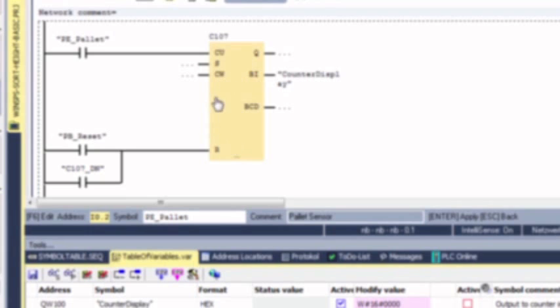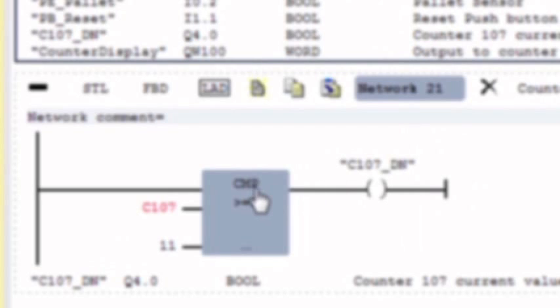Then you have a reset function. We have the operator's push button that can reset the counter, or it can automatically reset when we get our counter done bit — which is a bit we designed using our compare statement. We said if the current counter value equals 11, then output to the counter done bit. Outputting to that done bit would make the reset rung true, which would reset the counter.